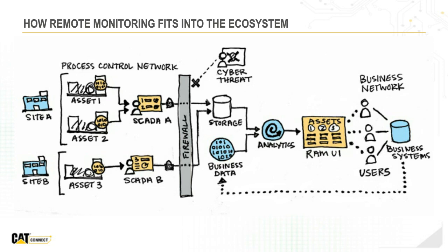We had an interesting use case recently that shows a key difference between remote monitoring and SCADA. We alerted a customer to change their air filter, and they said there was no issue. But we were trending and predicting an air filter blockage before the alarm went off on the SCADA system, giving them more time to plan, especially at a remote location.